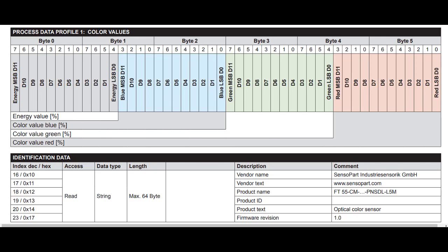And you can see here in IO-Link, you have the energy value, the blue, green, and red data, so you can set up the tolerances like color mode in your PLC. And again, let the sensor do the best fit.